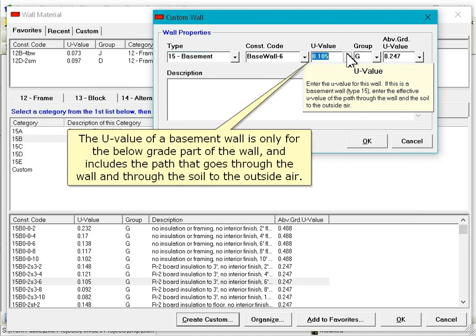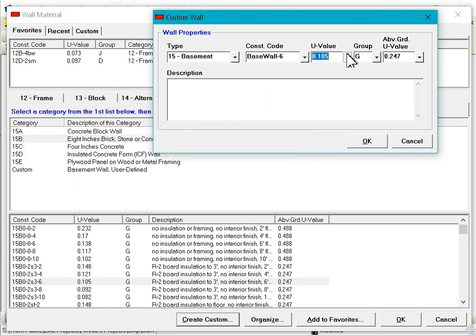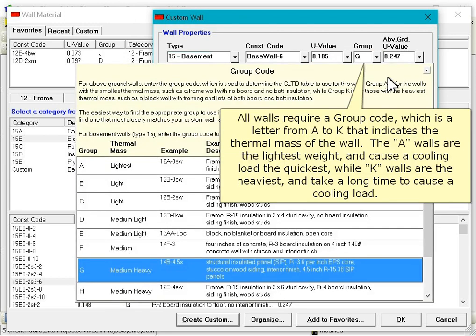The U-value of a basement wall is only for the below grade part of the wall and includes the path that goes through the wall and through the soil to the outside air. All walls require a group code which is a letter from A to K that indicates the thermal mass of the wall. The A walls are the lightest weight and cause a cooling load the quickest, while K walls are the heaviest and take a long time to cause a cooling load.